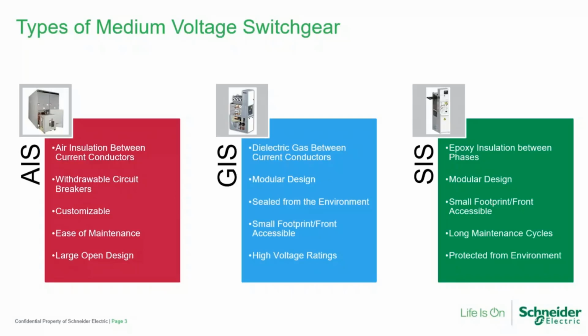If we move to the right, we're moving to a little bit newer style of switchgear, gas insulated switchgear. Gas insulated switchgear has been prevalent in the high voltage and utility market for quite a while, but started to see some entrance into the medium voltage market. And when I say medium voltage, I'm talking about anything from 1,000 volts up to 38,000 volts of nominal voltage. GIS started to see its entrance into the medium voltage market sometime in the 90s, depending on where you were, either in the world or in the US.